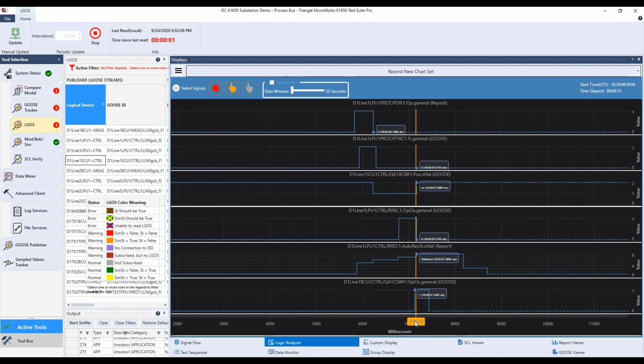Now he is in the state circuit breaker closed. He waits for the reclaim time to make sure that there is not a retrip again. And after the reclaim time, he went to the state successful. He waits for the ready time, and after the ready time, we are back to the state ready. So the recloser is armed again. There we can nicely analyze that everything behaves as we have designed it. And with that, I hand over to Jim for the final wrap-up.